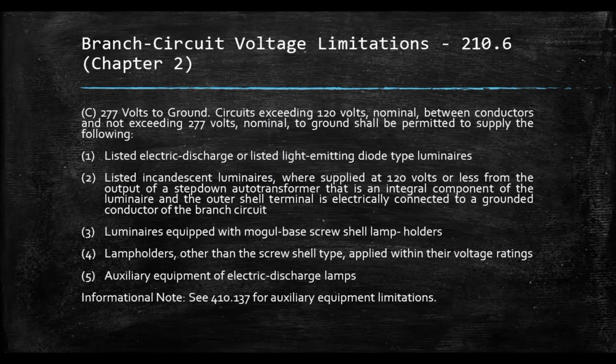Branch circuit voltage limitations, 210.6 from Chapter 2. Letter C, 277 volts to ground. Circuits exceeding 120 volts nominal between conductors and not exceeding 277 volts nominal to ground shall be permitted to supply the following.